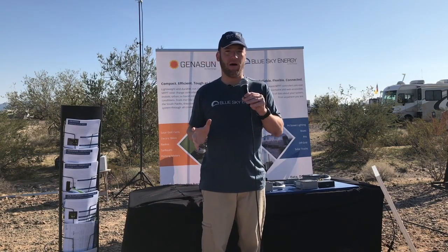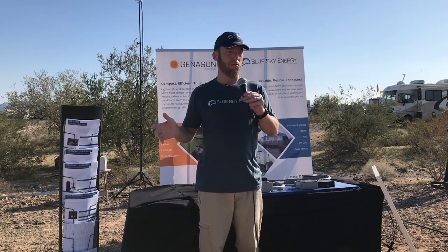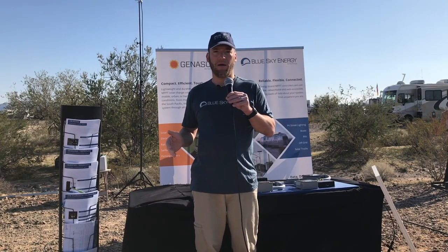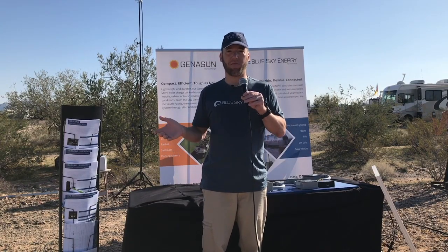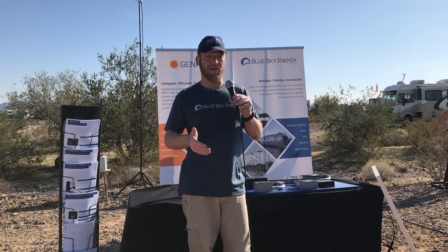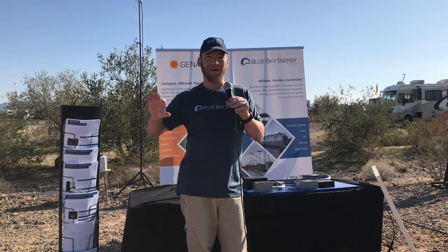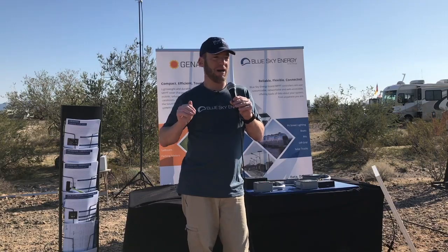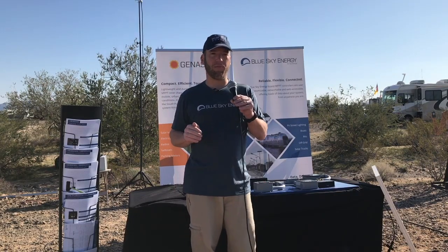So a lot of battery manufacturers will specify how much power is that when it becomes redundant. Our factory default is about 1.5 amps per 100 amp hours of capacity. Full River, I believe, specifies 2 amps per 100. Lifeline specifies 0.5 amps per 100. So it does vary on what each manufacturer's float transition set point could be.